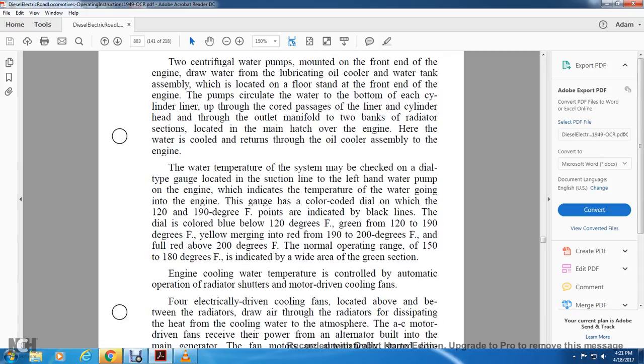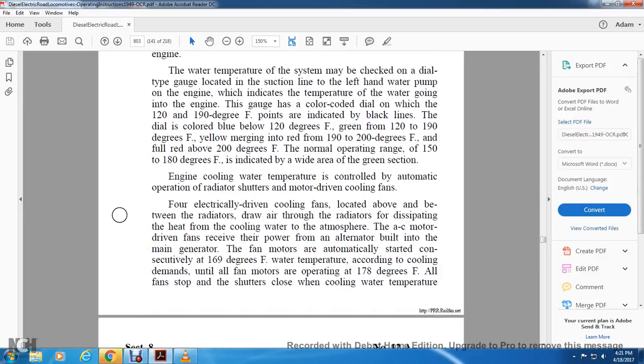The water temperature may be checked with the dial-type gauge located in the suction line at the left-hand water pump on the engine, indicating the temperature of water going into the engine. The gauge may be color coded, with the dial on which the 120 to 190 degrees Fahrenheit points are indicated with black lines. The dial is colored blue below 120 degrees Fahrenheit, green from 120 to 190 degrees, yellow merging with red from 190 to 200 degrees Fahrenheit, and red above 200 degrees Fahrenheit. The normal operating range, 150 to 180 degrees, is indicated within the wide green section. Engine cooling water temperature is controlled by automatic operation of the radiator shutters and the motor-driven cooling fans.